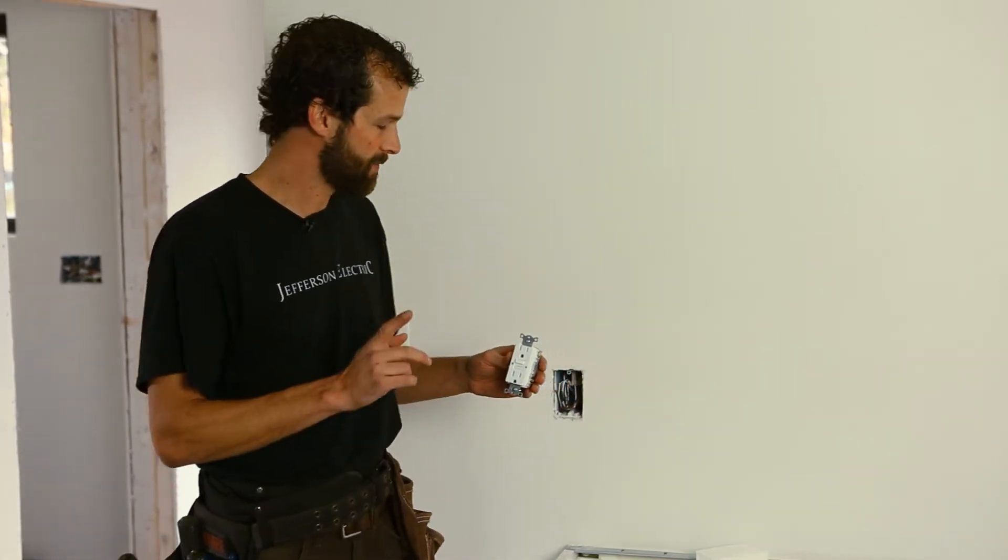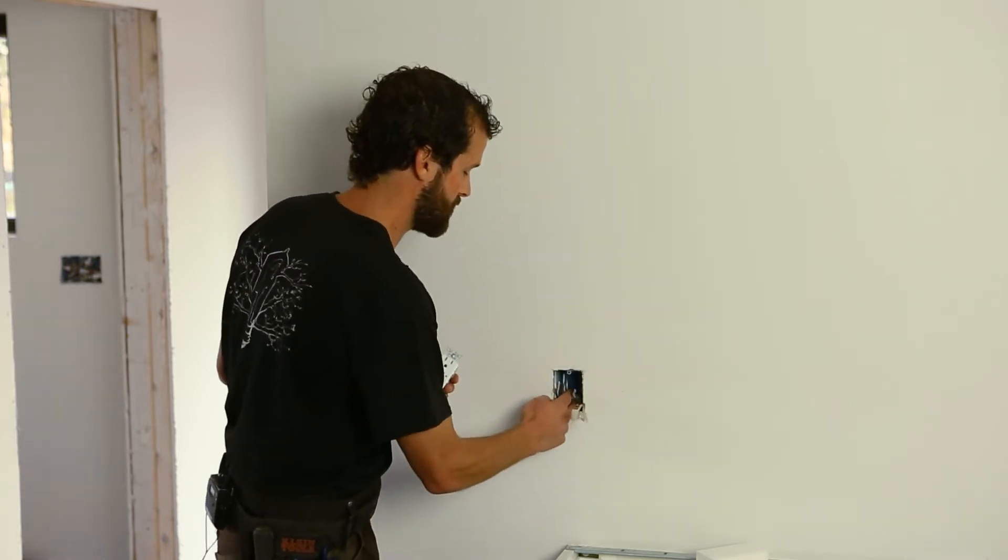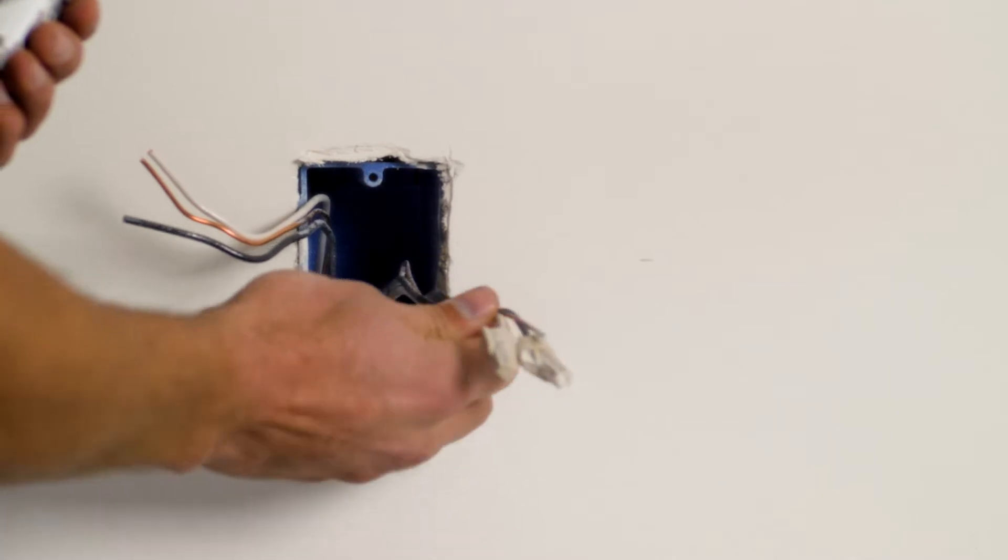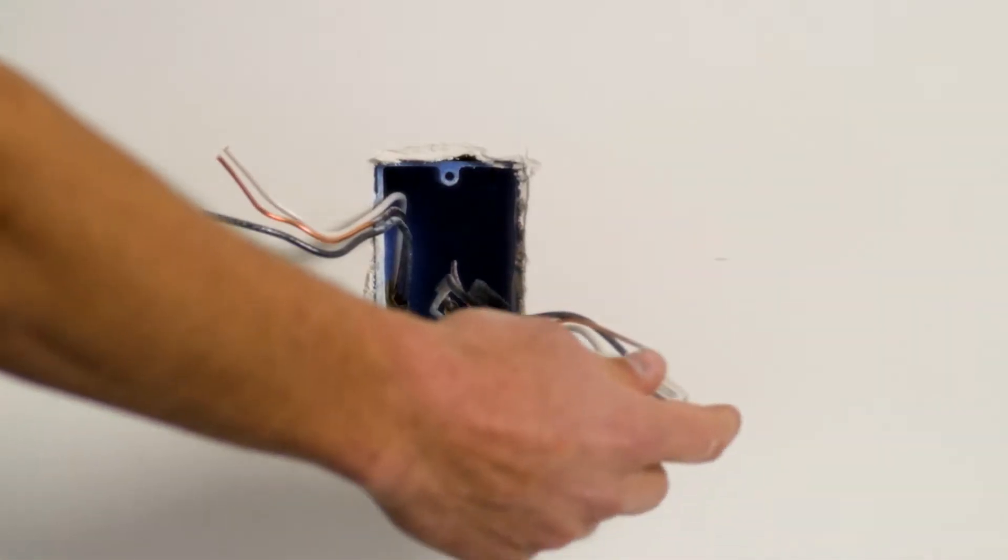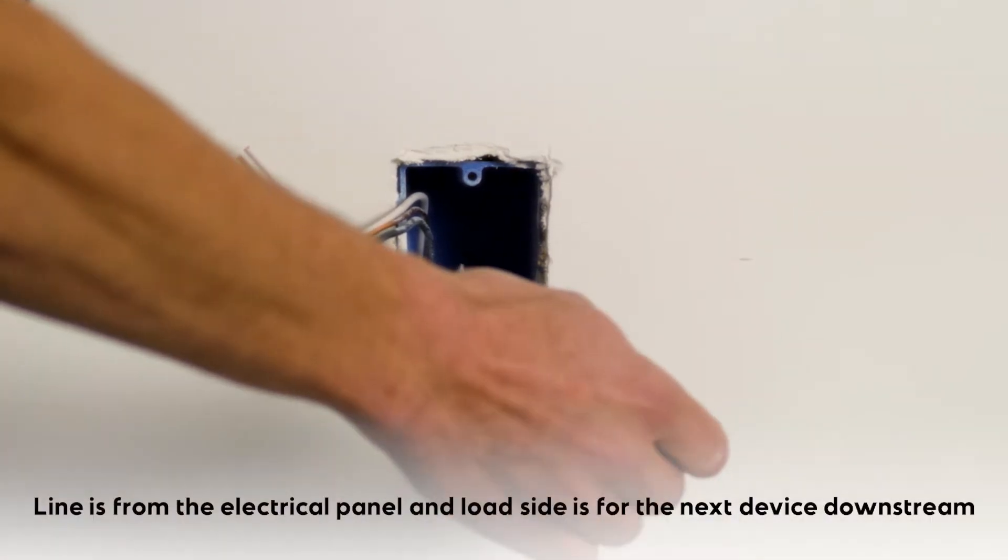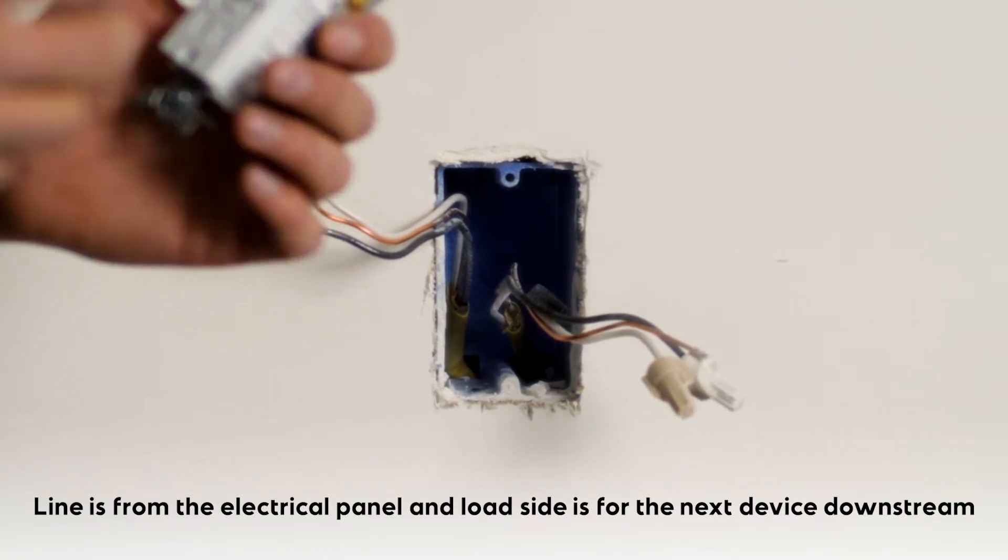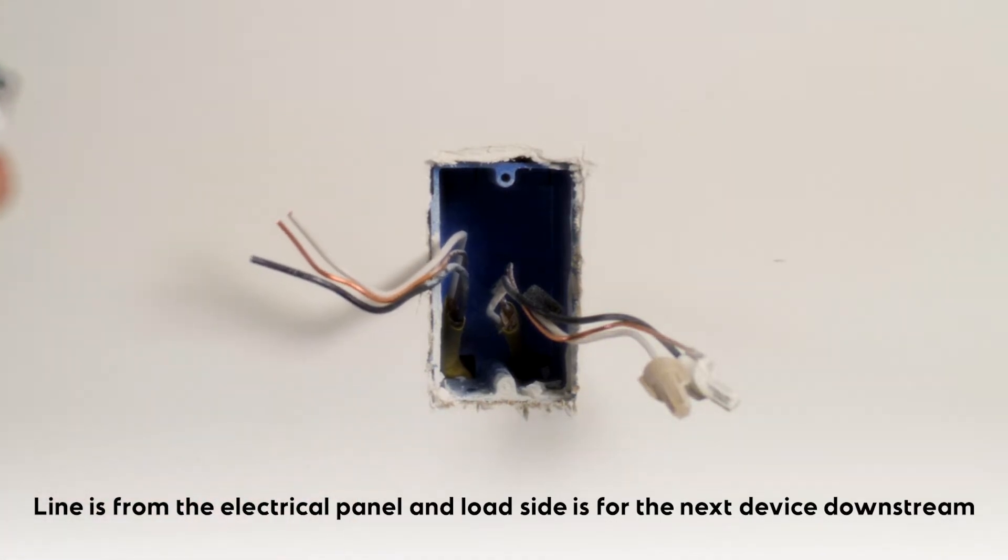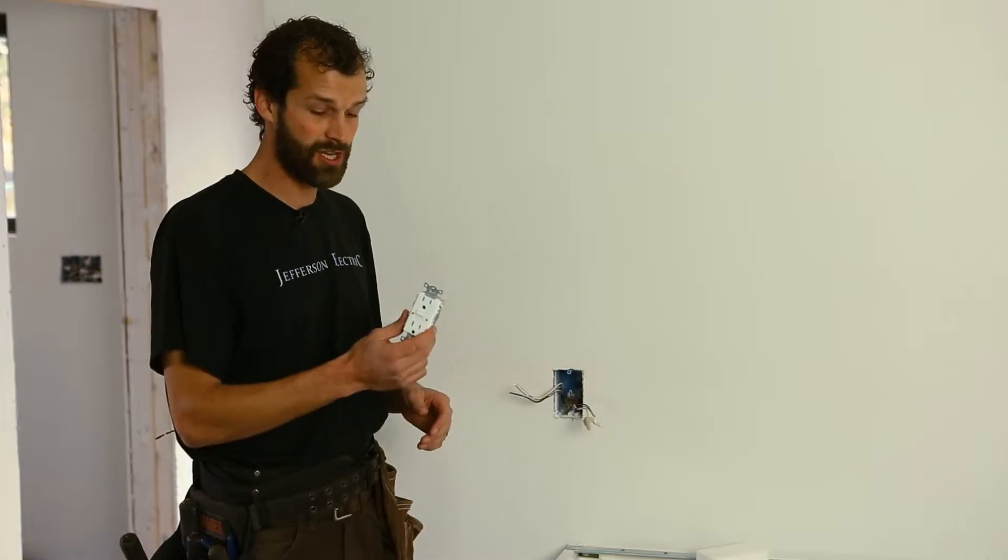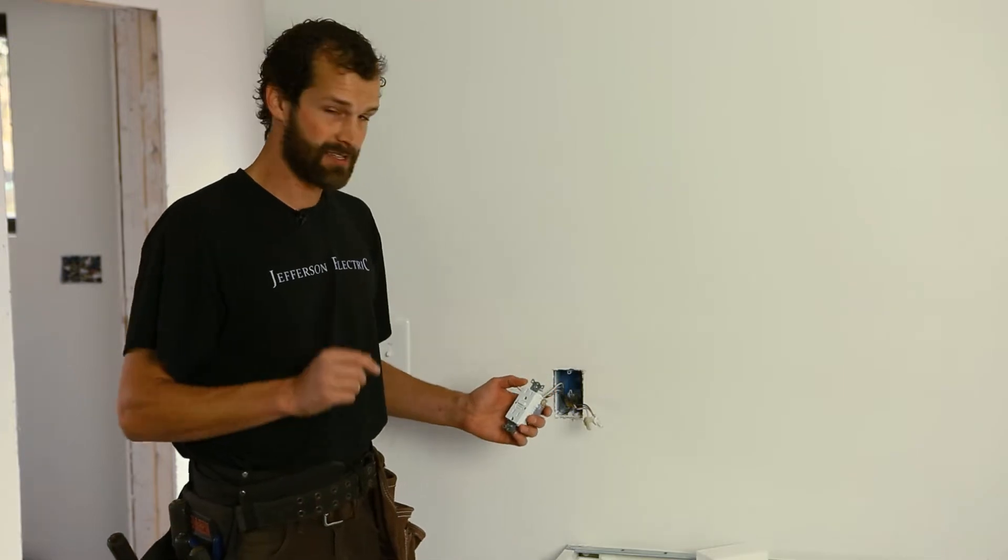In this case, we're not only protecting this location with the GFCI, but you'll see we've got two sets of conductors, two cables coming into this box. The first is marked with a flag of black tape and made safe with wire nuts - that's our line side coming from the panel, our power source. The second is our load side, going to the next device downstream. GFCI costs about $18 at a retail hardware store, so utilizing one GFCI to protect multiple locations is a cost-effective approach.